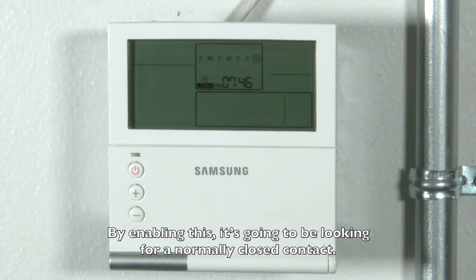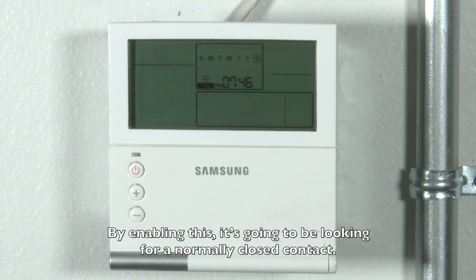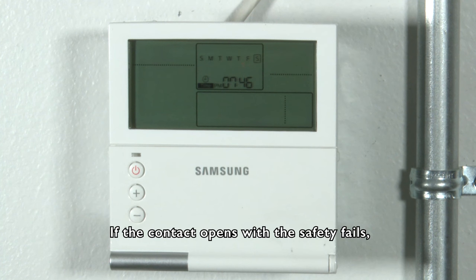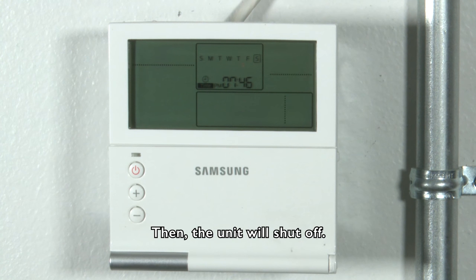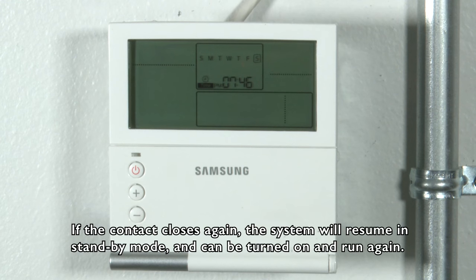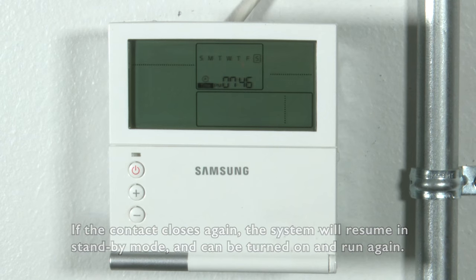By enabling this, it's going to be looking for a normally closed contact. If the contact opens when the safety fails, then the unit will shut off. And if the contact closes again, the system will resume in standby mode to be turned on and run again.